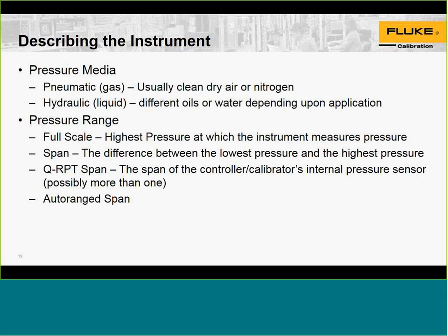You don't want it to stop at 0 if you have negative gauge pressures or sub-atmospheric pressures. Span is a calibration branded term. You can have multiple RPTs available in an instrument, and a user set span that is less than or equal to the RPT span, and that is the rangeability of the RPT.